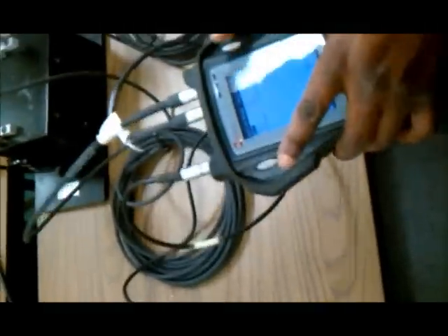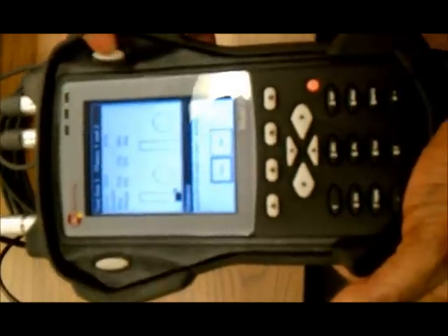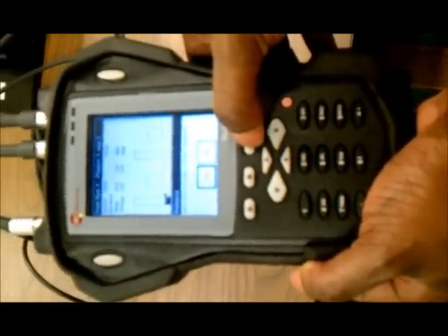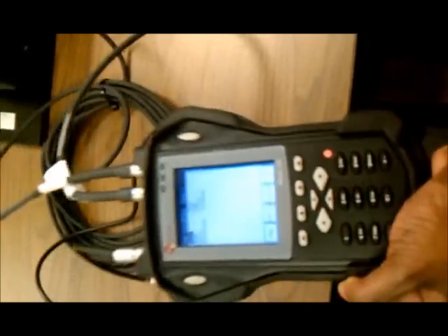So we'll start her up again, and we will hit the fire key. What we want to see is a change in our mils reading, which we have, because it's going from 2-something to 10-something, which means we've had more than our 30% change. So we'll hit our fire key to capture the reading, and it's going to ask us if we want to keep the trial weight attached or not. In this instance, we're not going to keep it attached because it's easy to remove. And we're going to put it on our second plane.